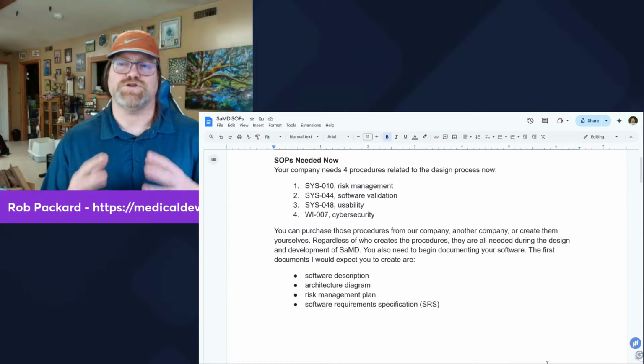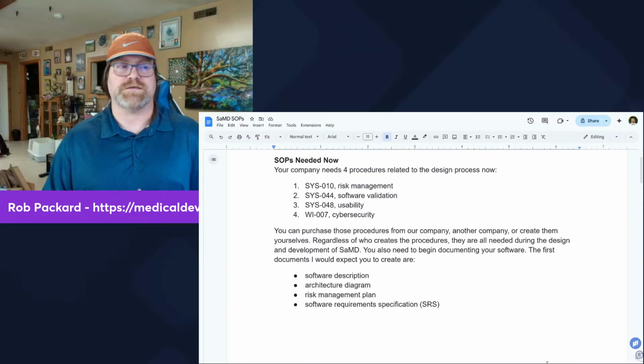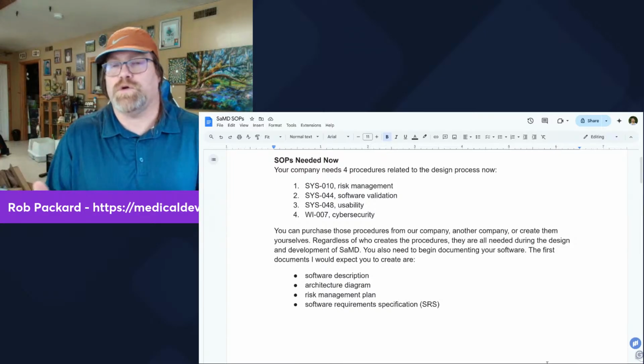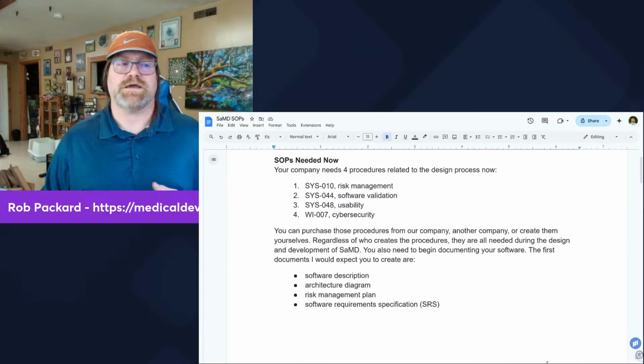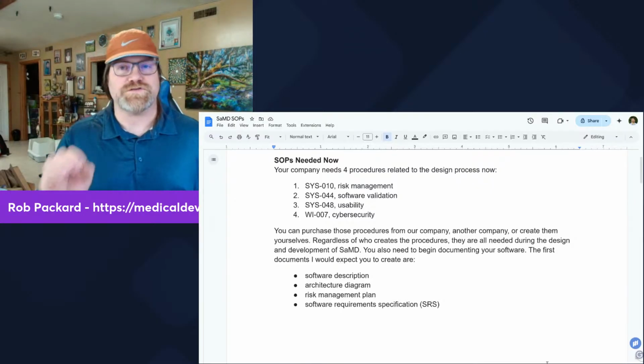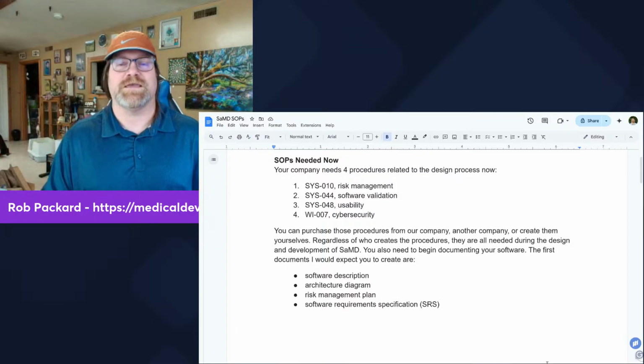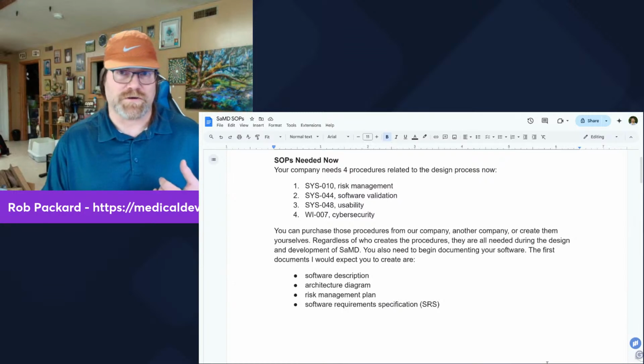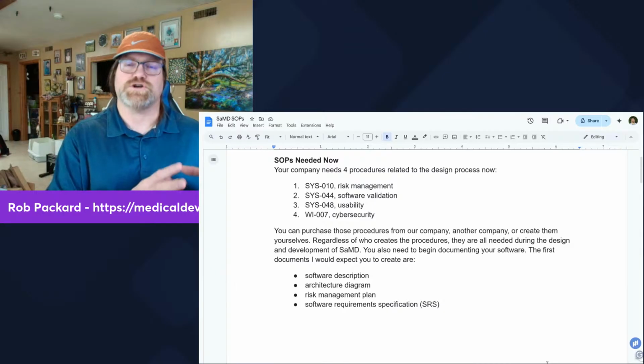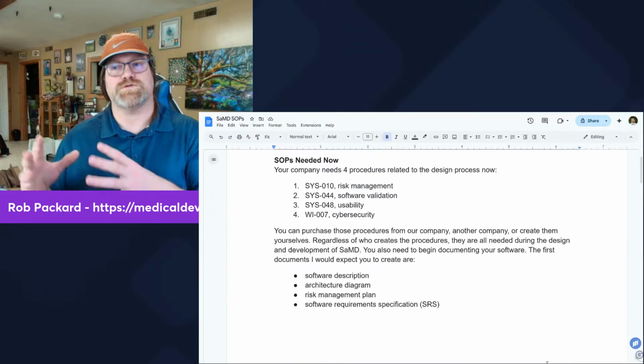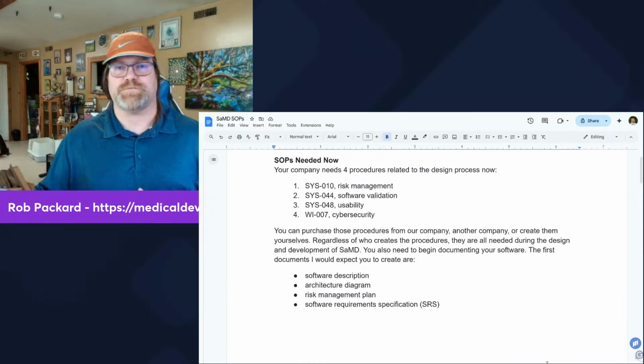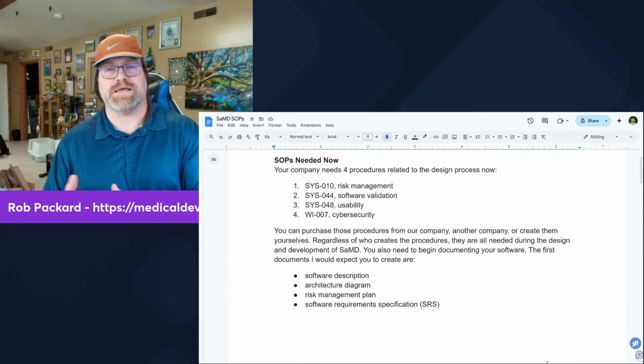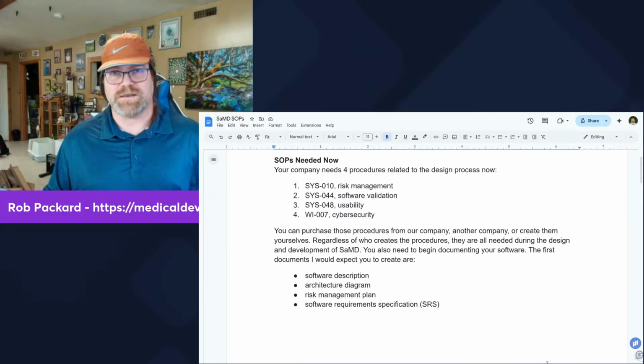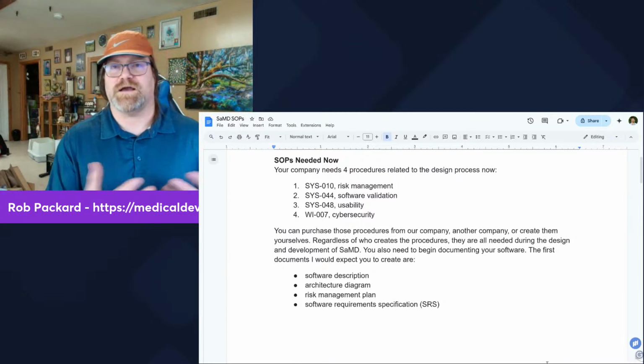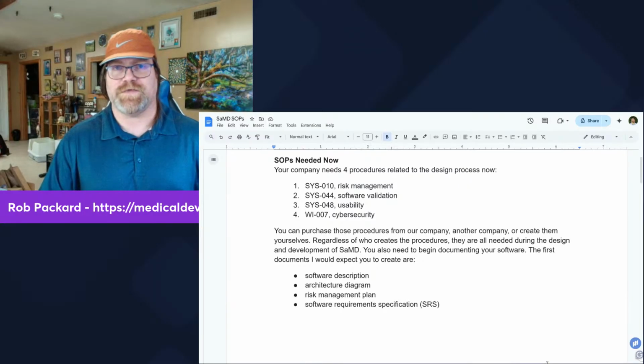And then the first 4 documents that you should be creating as sort of your inputs to the process. What is the software description? You've got to describe it so we know what we're coding, what we're trying to design here for software. We've got to explain what the architecture diagram is going to look like. This is a critical strategic design. It's not something you just throw up on there in 10 minutes. It's a critical strategic design because you have to design it for security, and you have to identify what functions of the software in your architecture are going to be non-device functions, which ones are going to be low risk, class A, which ones are going to be medium risk, class B, and if you have a life-threatening, life-supporting device, is there a class C component to this software? And instead of writing all your documentation to one of those classifications, you write the documentation for the module articulated in the architecture and the software description to the level of risk of that particular module. So that's how you should be thinking about architecture diagrams.